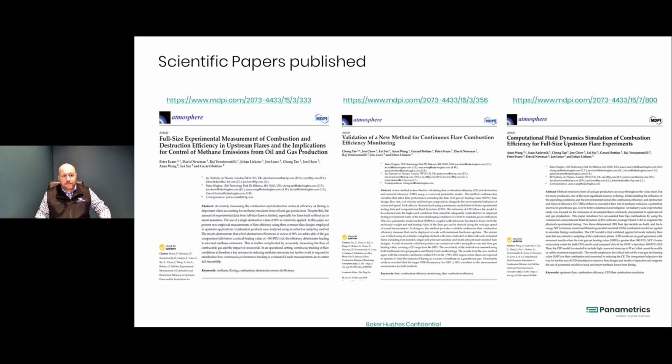Now, just going to say, I've gone through these last slides fairly quickly. I don't want to make you think that this was a simple test with minimal impact for operators or regulators. So for those that have more interest in reading through this study and how we gained the data and analyzed it, I highly encourage you to read through these 3 different academic papers that Panametrics had published with BP. The first paper sets up the methodology of the test and the implications for controlling methane emissions on flares, along with showing the DRE above 98% is possible, though it highly depends on the net heating value of the vent gas and crosswind conditions.